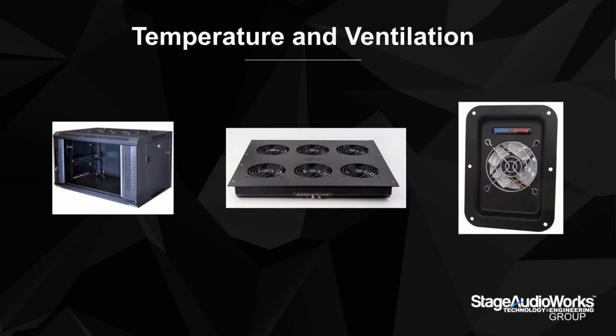The presence of dust and inadequate ventilation can severely damage electronic equipment. So just sticking a bunch of amps in a rack in a corner somewhere with no proper ventilation, or the back of it is against the wall, or the doors are closed and locked, can cause serious issues with the equipment. The longevity might be affected because the components are rated for a certain temperature. They won't fail immediately, but over time, if they run out of spec for a long period of time, obviously the longevity of the product will be affected.